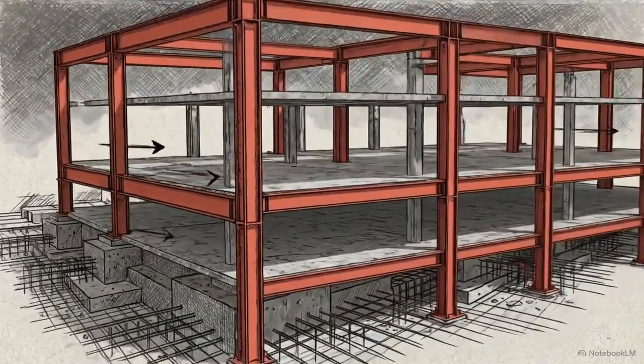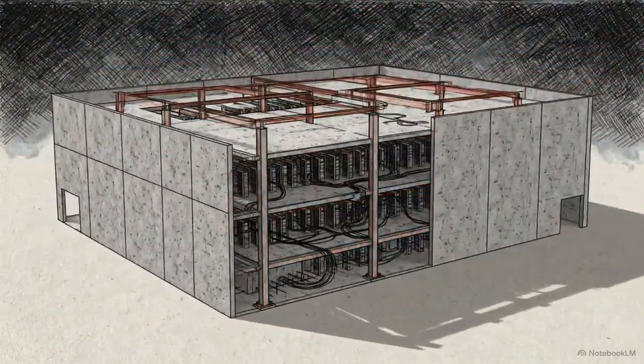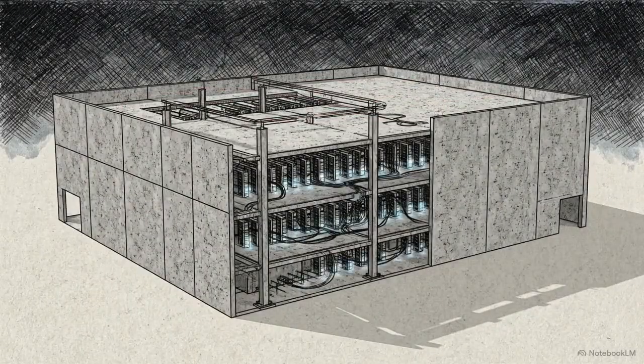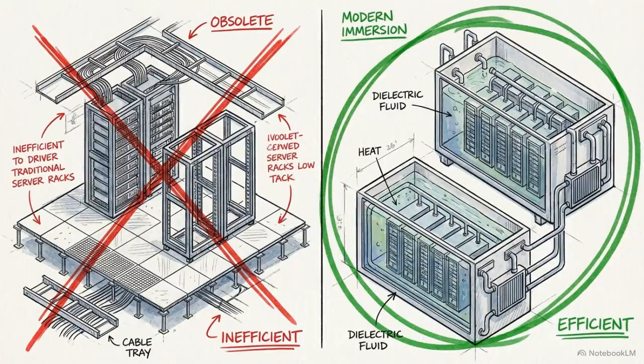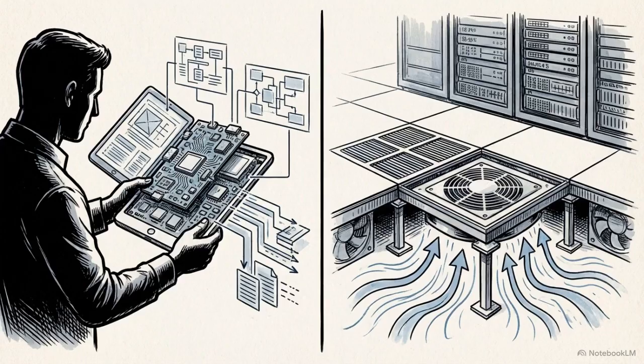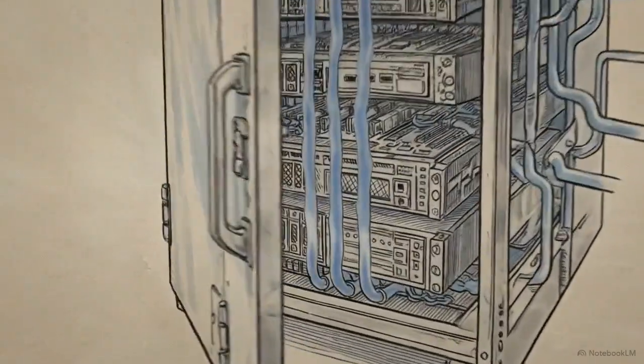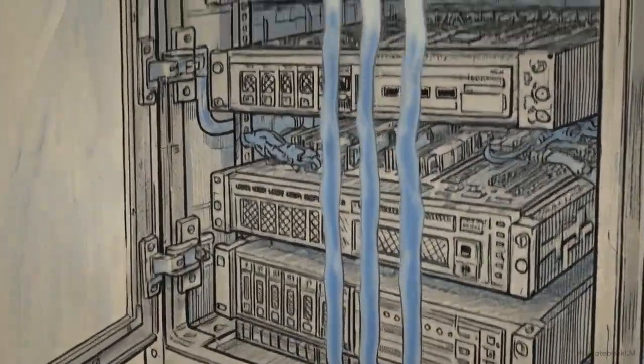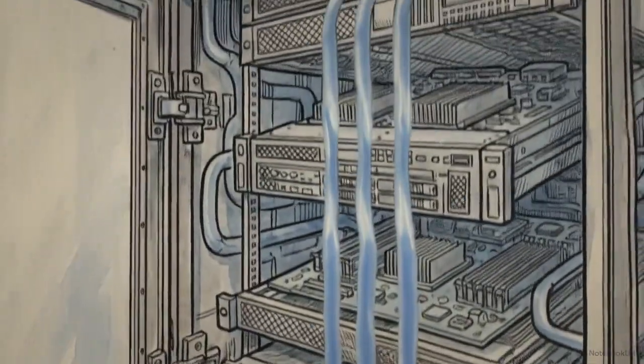Two-phase immersion demands the absolute highest initial capital investment and is generally only viable for strictly purpose-built infrastructure. Immersion cooling forces an operational reinvention of the data center, but it provides the only mathematical path to securing maximum compute density for flagship AI workloads operating at scale. Selecting a liquid cooling architecture depends entirely on an organization's specific operational footprint. Consider the retrofitter. This is an IT leader tasked with dropping high-density AI workloads straight into an existing traditional data center. Their optimal path is direct-to-chip cooling. It enables a phased deployment that upgrades individual racks without ripping out the existing raised floor architecture.